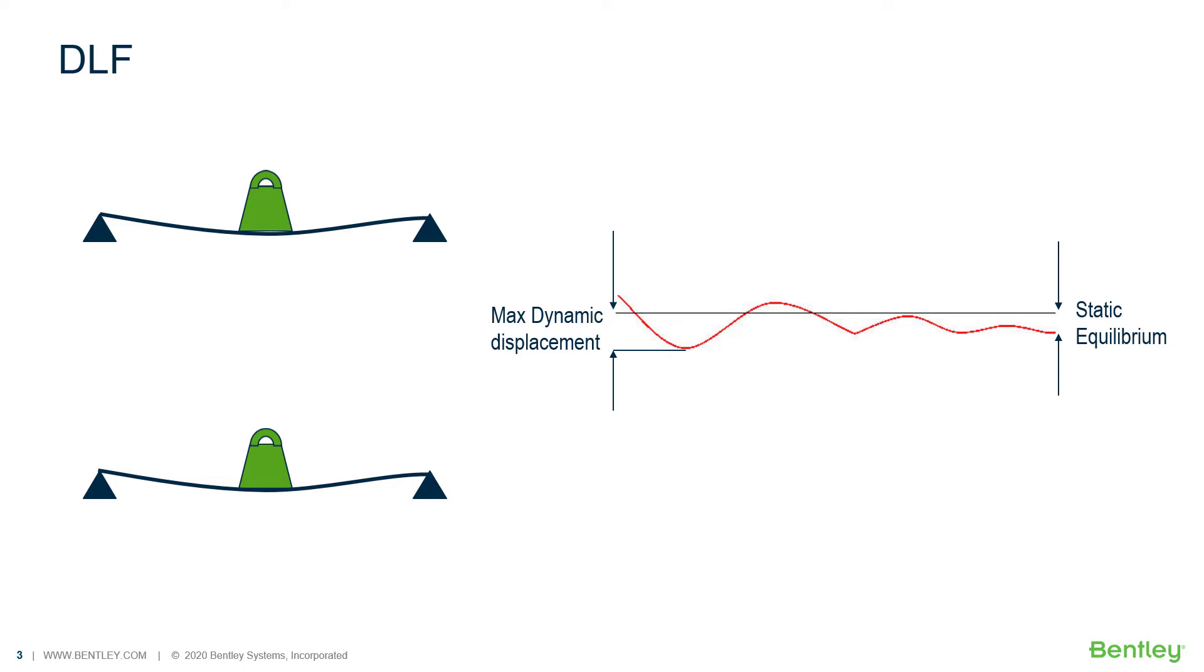The magnitude of the DLF will range between one and two, and it's dependent on the time history of the load and the natural frequency of the structure, and this is only true for instantaneously applied loads, so it's a maximum conservative value. In the ASME codes, there is a static equivalent approach that simulates dynamic events by taking the static load and multiplying it by the DLF.